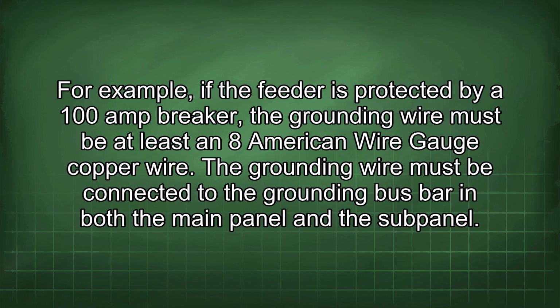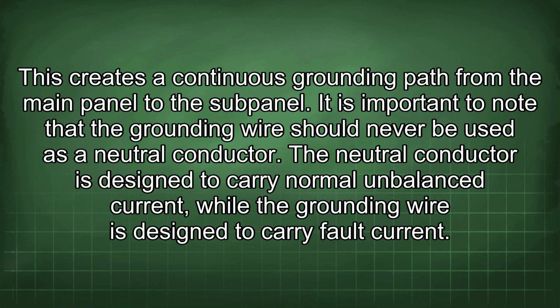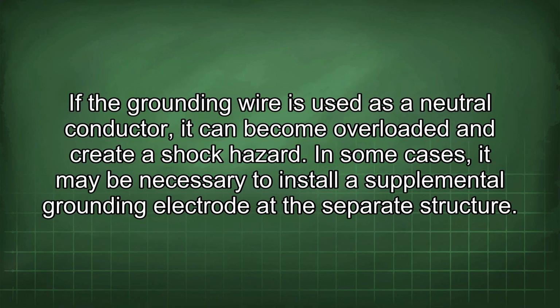The grounding wire must be connected to the grounding bus bar in both the main panel and the subpanel. This creates a continuous grounding path from the main panel to the subpanel. It is important to note that the grounding wire should never be used as a neutral conductor. The neutral conductor is designed to carry normal unbalanced current, while the grounding wire is designed to carry fault current. If the grounding wire is used as a neutral conductor, it can become overloaded and create a shock hazard.